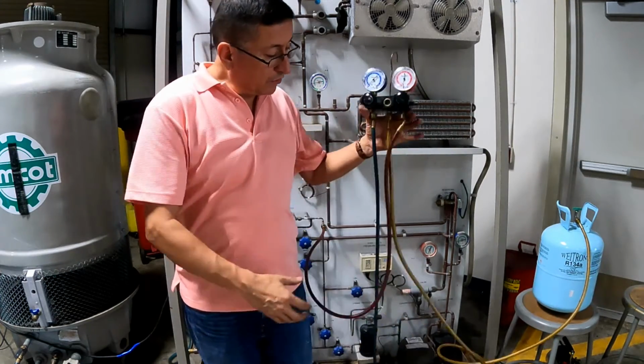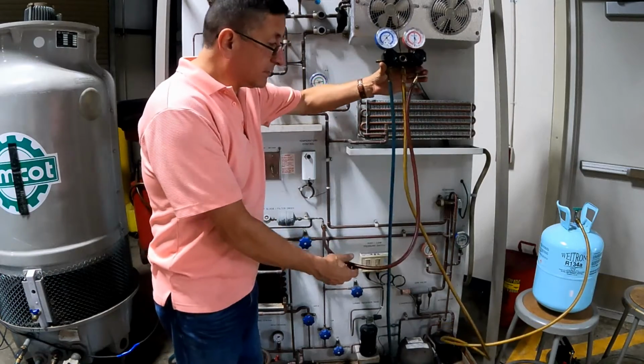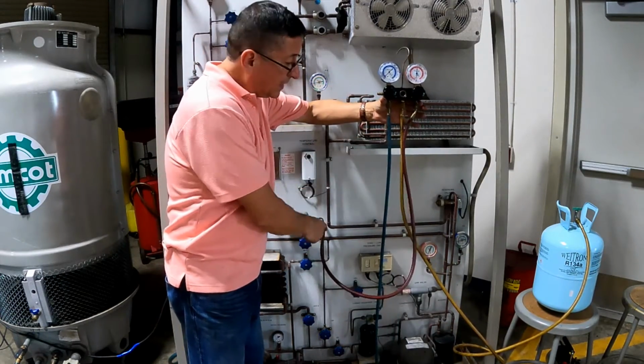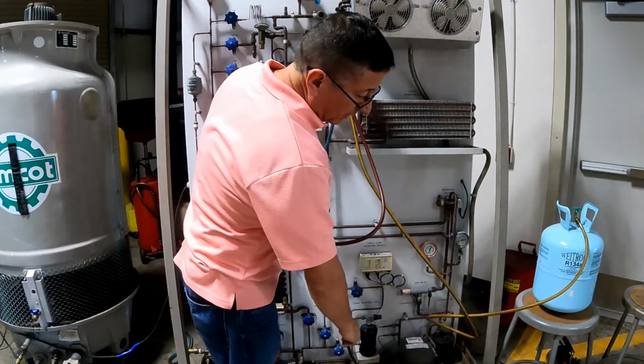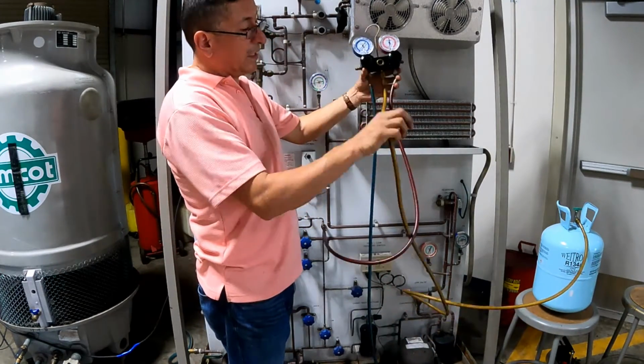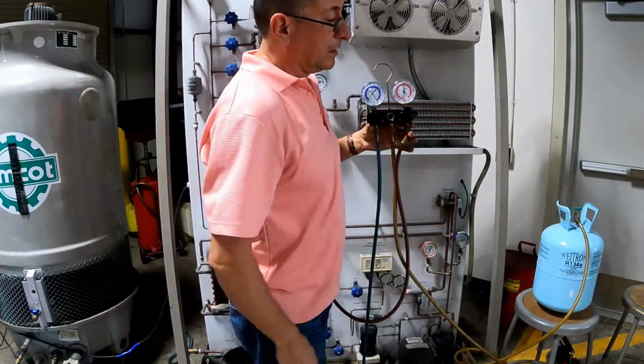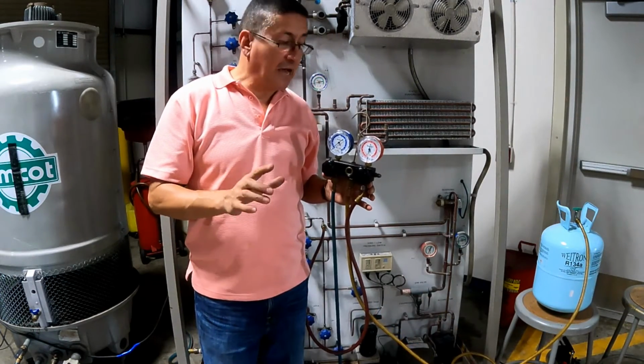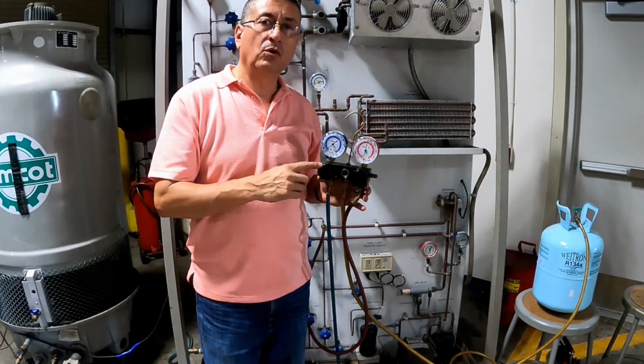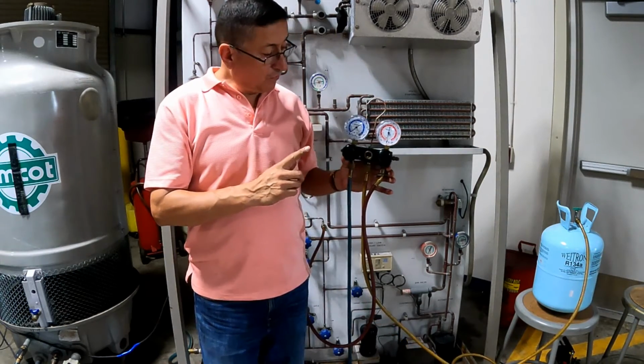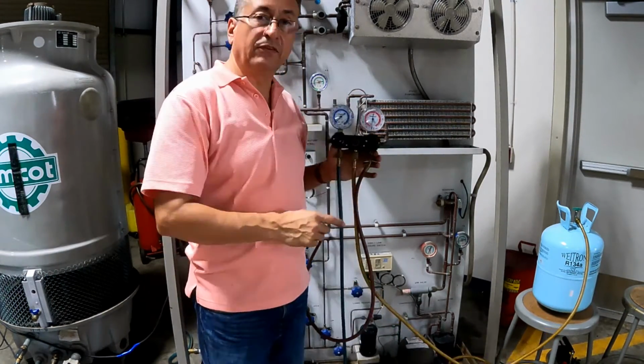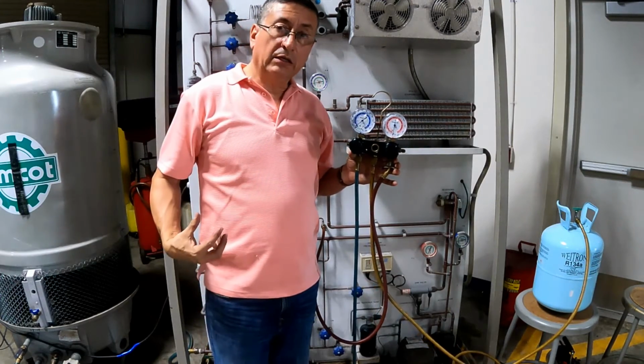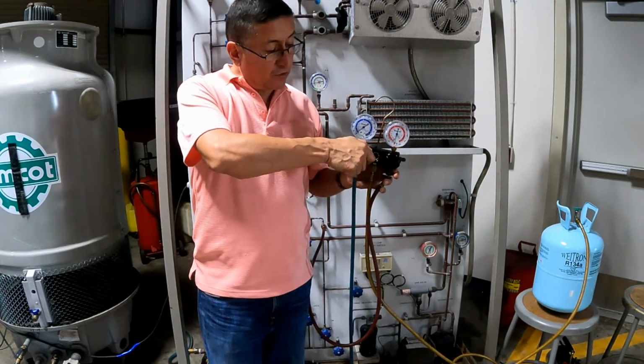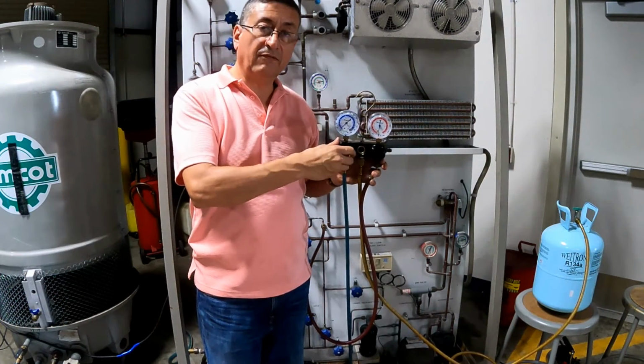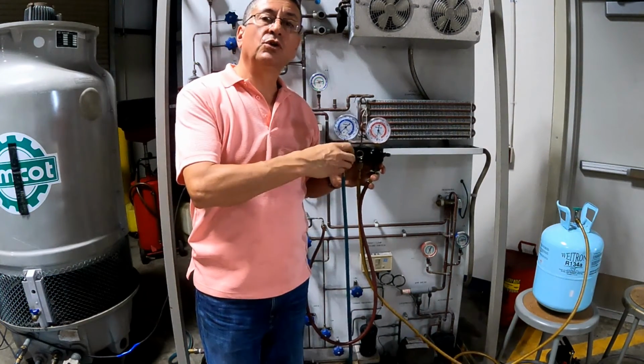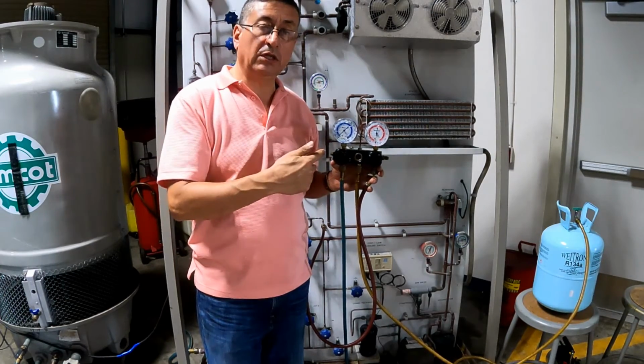To put the refrigerant back, we are going to connect our set of gauges. It's exactly the same. The high pressure line in the high pressure side, the low pressure line in the low pressure side of the compressor, and the middle one connected directly to the recovery tank. Normally, the refrigerant is added in the vapor side through the low side of the compressor. For that reason, we are going to open the valve of the cylinder. We are going to start the air conditioning equipment, and after that we are going to turn on the valve of the low pressure side to introduce the refrigerant into the unit.